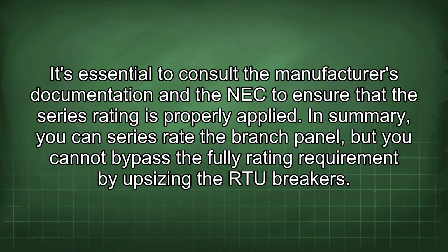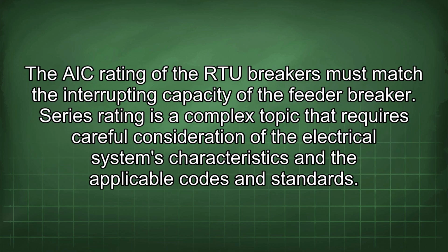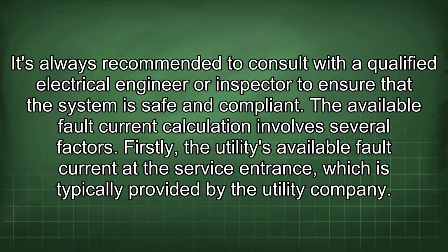In summary, you can series rate the branch panel, but you cannot bypass the fully rating requirement by upsizing the RTU breakers. The AIC rating of the RTU breakers must match the interrupting capacity of the feeder breaker. Series rating is a complex topic that requires careful consideration of the electrical system's characteristics and the applicable codes and standards. It's always recommended to consult with a qualified electrical engineer or inspector to ensure that the system is safe and compliant.